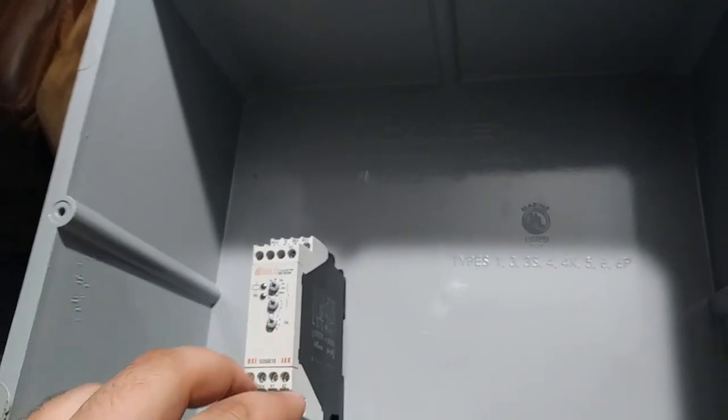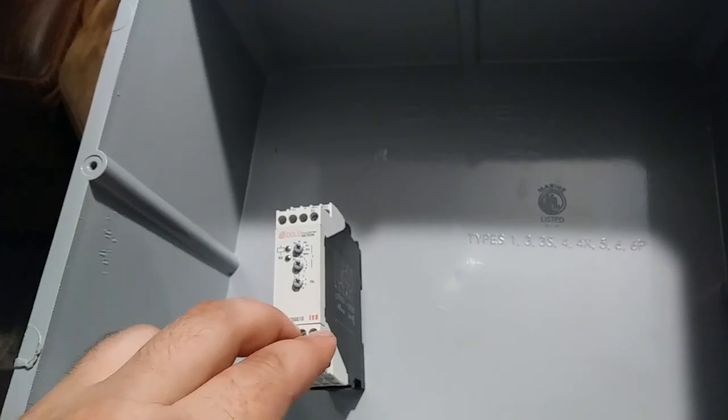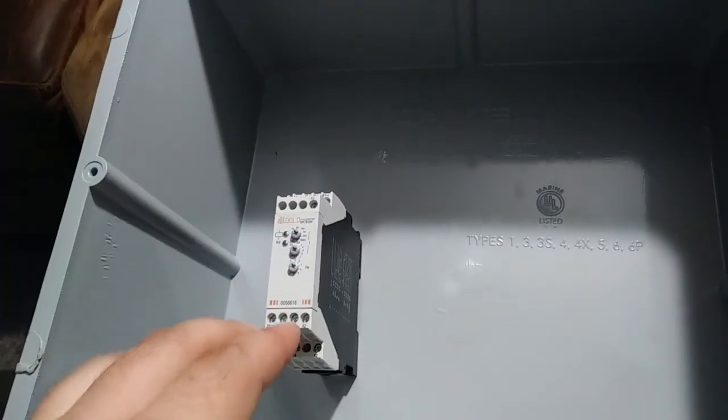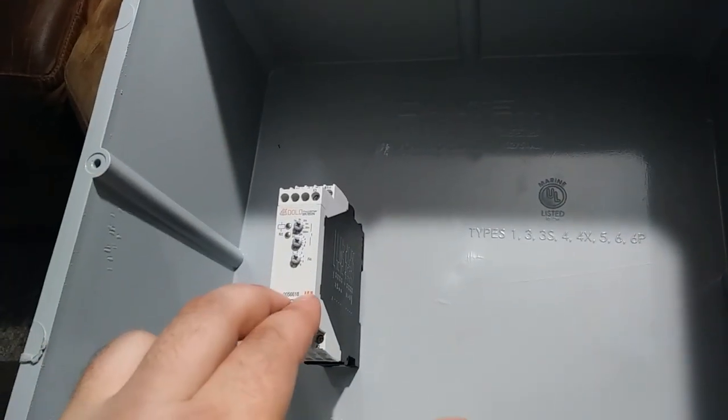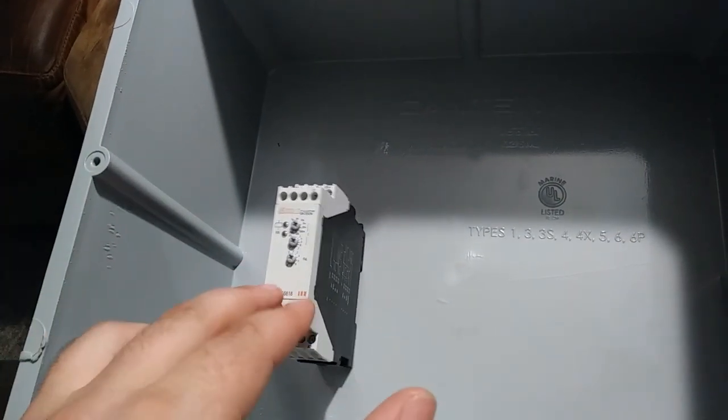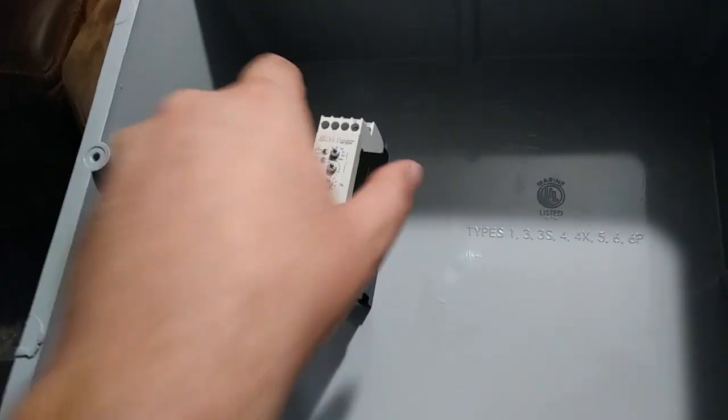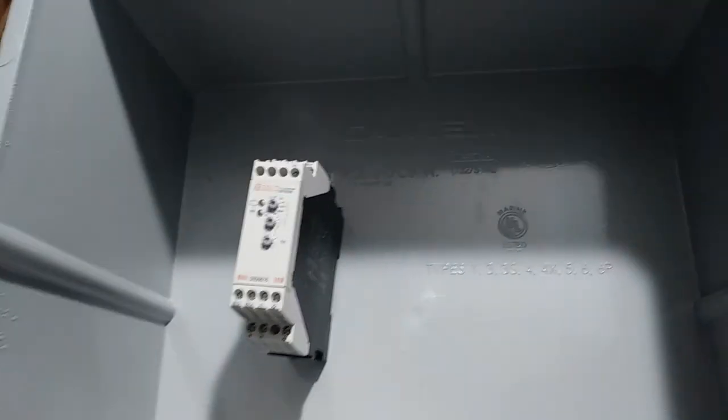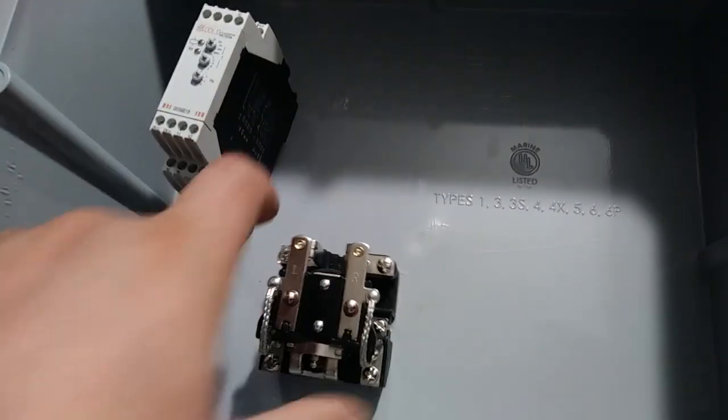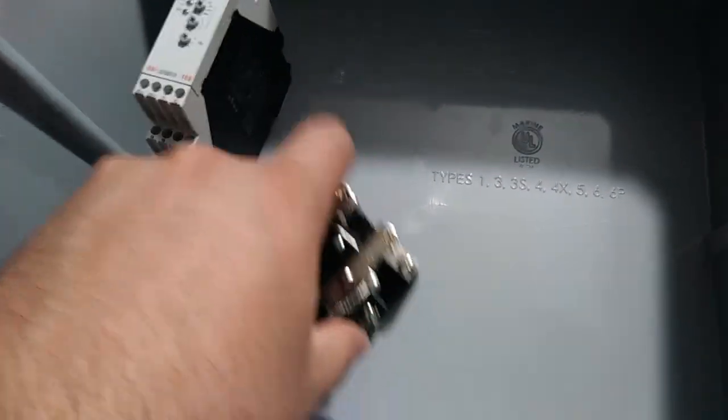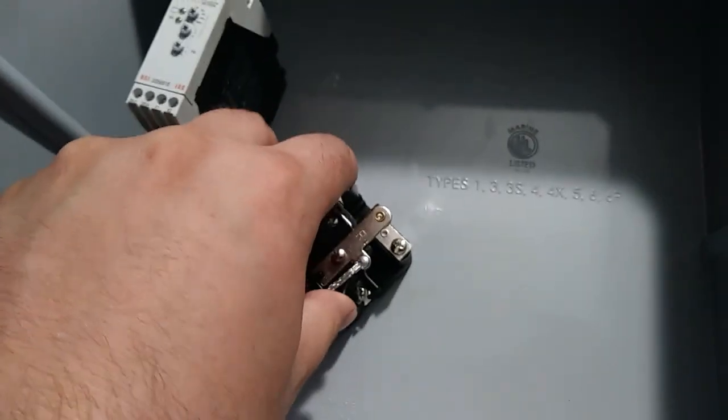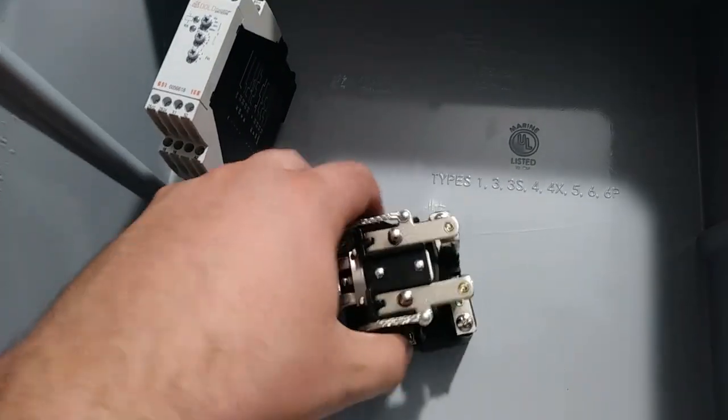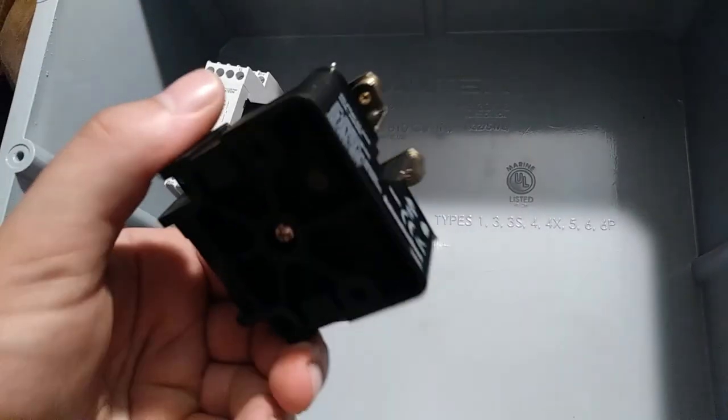as well as the heater, will be on the auxiliary, the heater enable, so it will shut off when the primary pump is off after four hours or three hours or whatever the customer decides. It's pretty simple and these relays themselves can't handle the pump amperage, so we'll be doing that with these general purpose relays, open contactors.